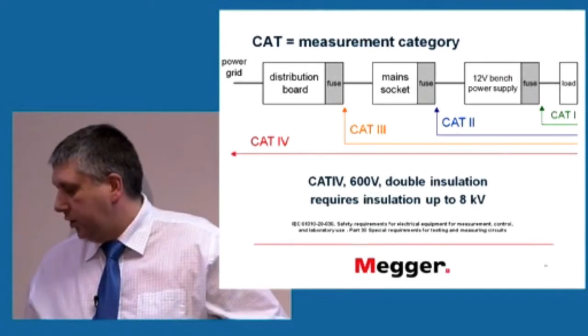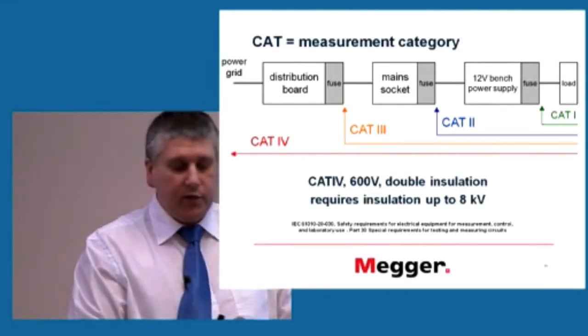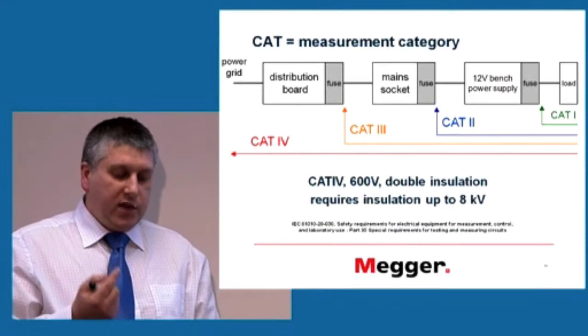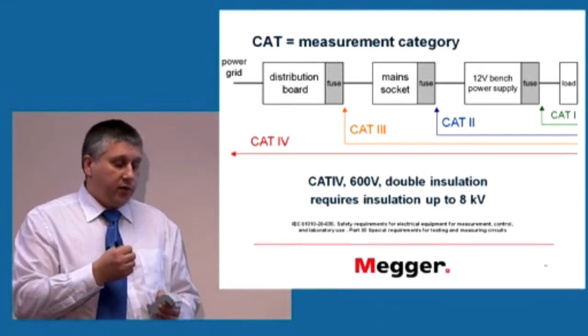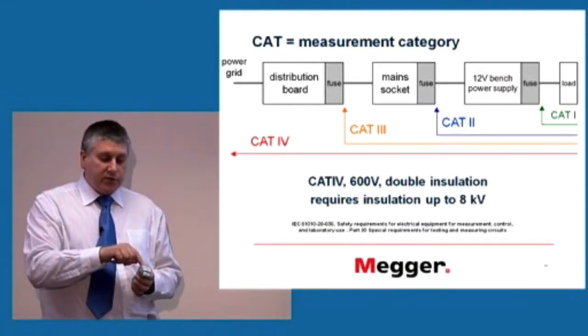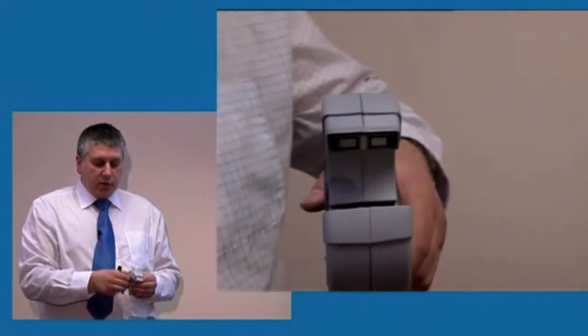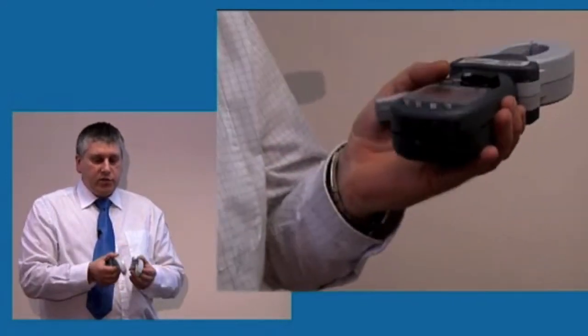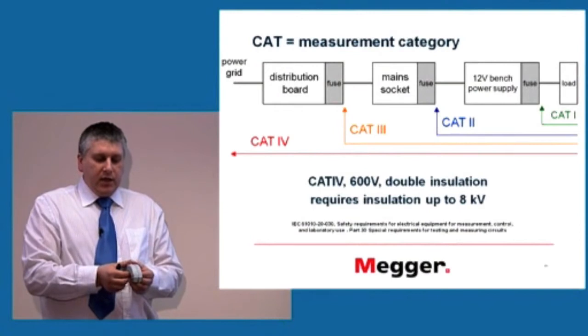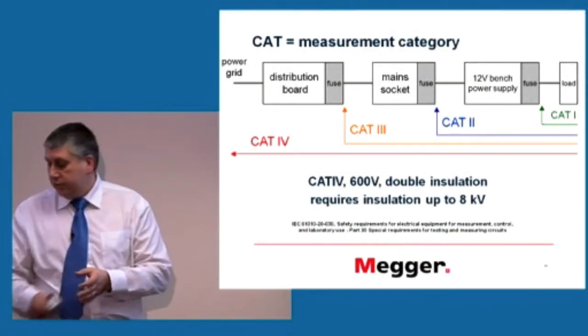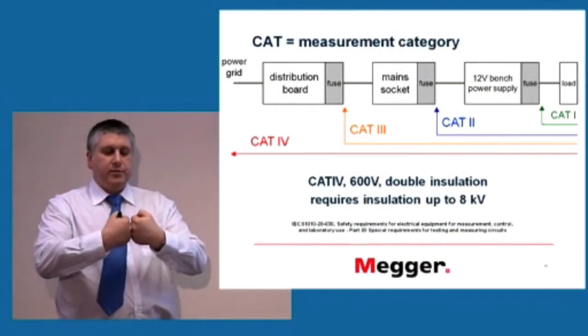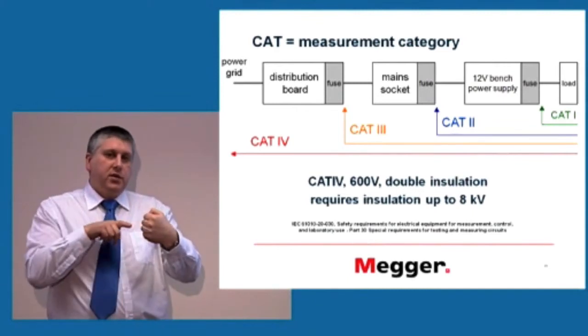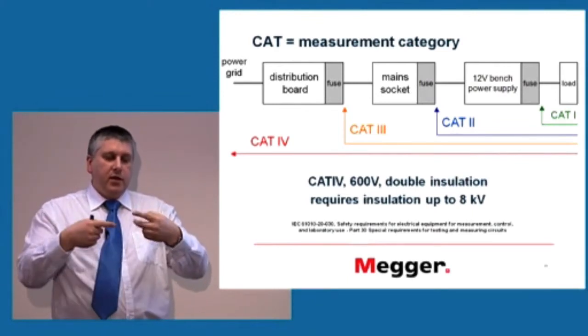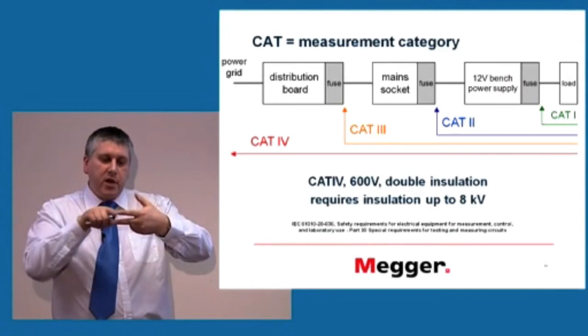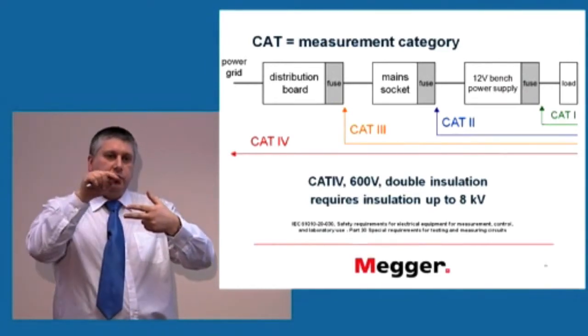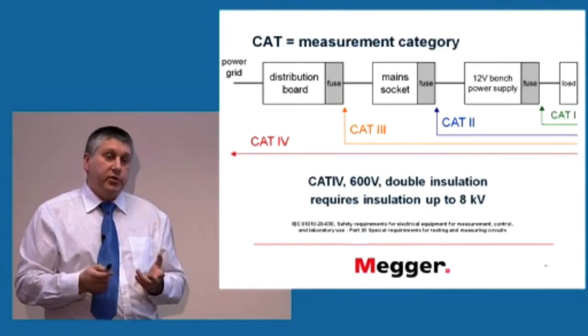One of the things I can show you, you can have a look at, is that the double insulation and the 8,000 volts insulation has to be between the outside and the inside, for example, of the core. So any plastic which goes around that, any casing, is designed in tongue and groove. So there's not just plastic which is butted, even if it's glued, where there's a possibility of voltage going there. There's always tongue and groove. So there's a much longer path between the outside wall and whatever is potentially connected to the system.